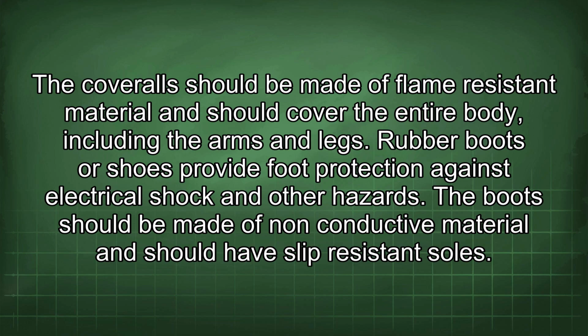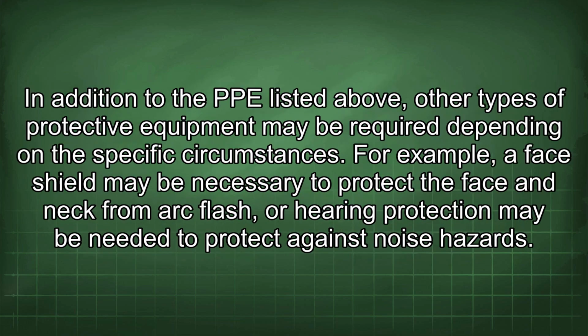The coverall should be made of flame-resistant material and should cover the entire body, including the arms and legs. Rubber boots or shoes provide foot protection against electrical shock and other hazards. The boot should be made of non-conductive material and should have slip-resistant soles. In addition to the PPE listed above, other types of protective equipment may be required depending on the specific circumstances. For example, a face shield may be necessary to protect the face and neck from arc flash, or hearing protection may be needed to protect against noise hazards.